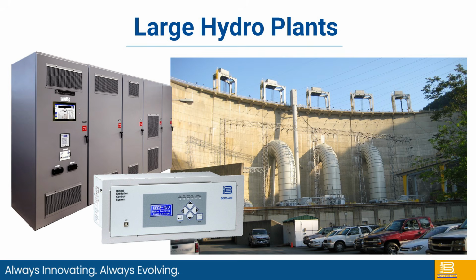It uses DECS 400s—started with DECS 300s, then upgraded to DECS 400s, and now I believe it has some DECS 450s on site. On the left here is an example with the DECS 450, but a plant like this could also use DECS 2100s. The DECS 2100 can go up to 10,000 amps, where our DECS 450 products top out at about 2,500 amps.